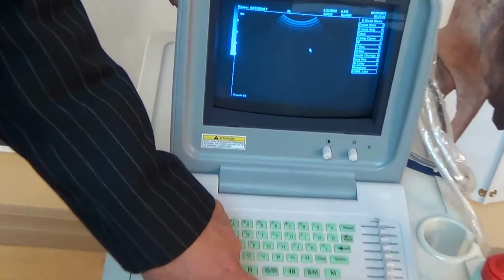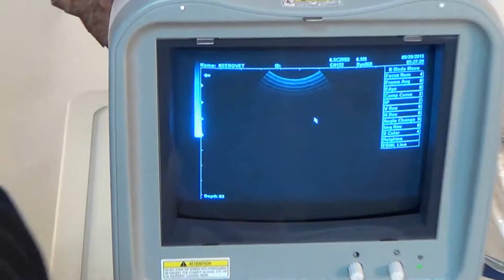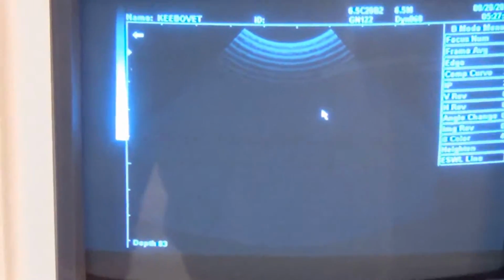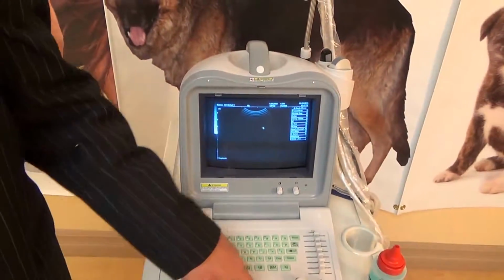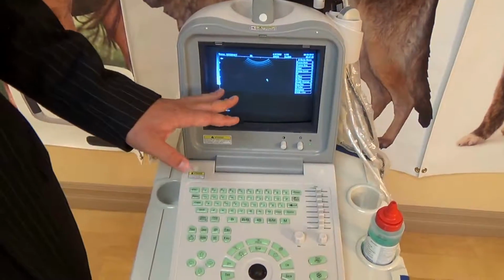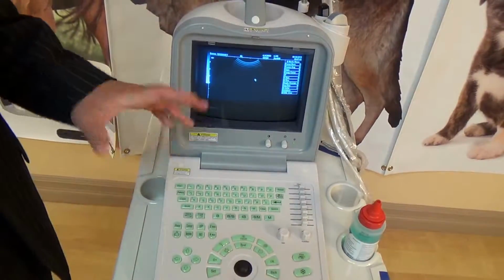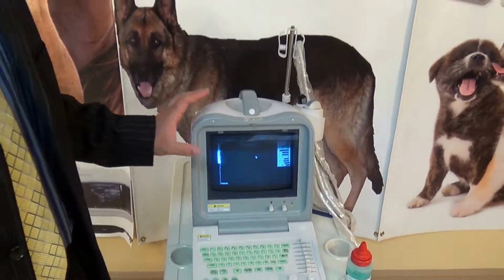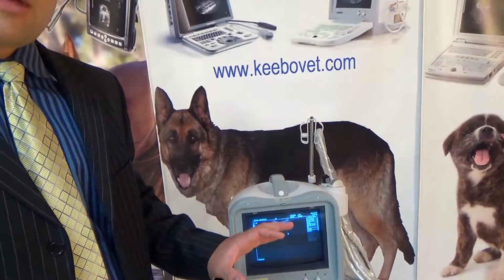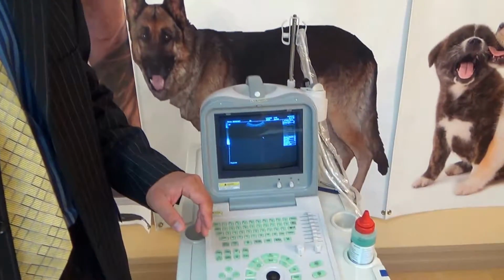So we start off with 1, you can have 2, 3, 4, and we can adjust the height of those depending on the number. So with the keys I can move it up and down, and with the focus button I increase the number. So focus basically helps you obtain a better image quality. If you have a lot of focus, that sometimes slows the machine down for the frame rate because the computer is putting together a better image.